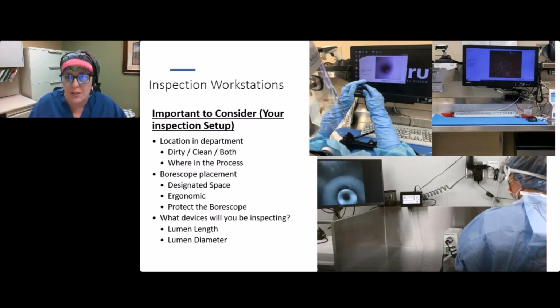So on the dirty side, we went through, is it an inspection tool? It is. And for us, we think of it as a verification of the manual clean. We want to catch that stuff real time as it's happening. We all have the mentality, it has to be clean. Otherwise, it's not going to be disinfected and sterilized. So we have to do that cleaning verification. And we have a 2-step program. One of that is the borescope inspecting that internal channel. And the other part is residual protein testing.